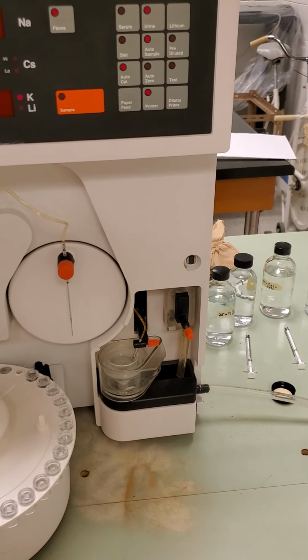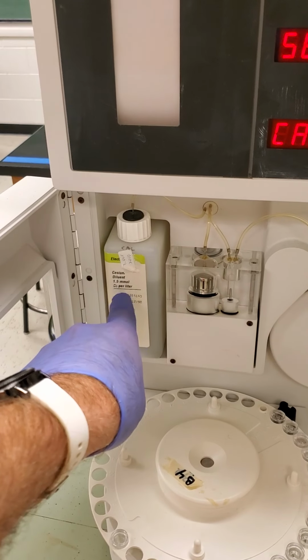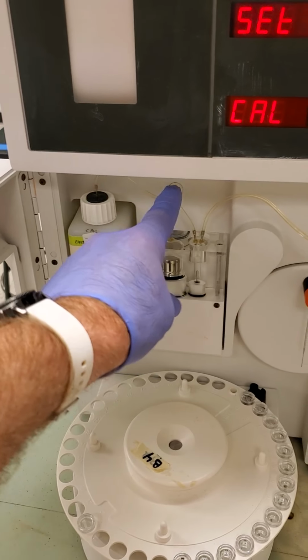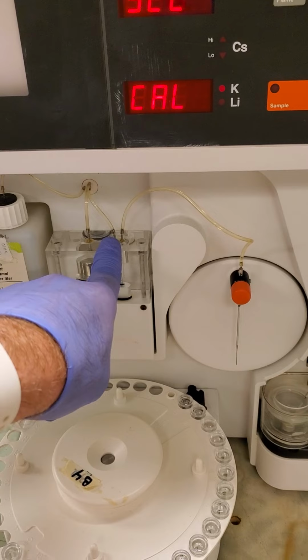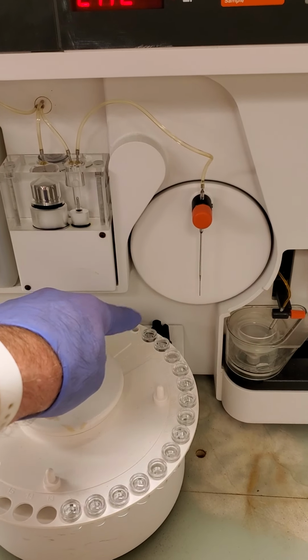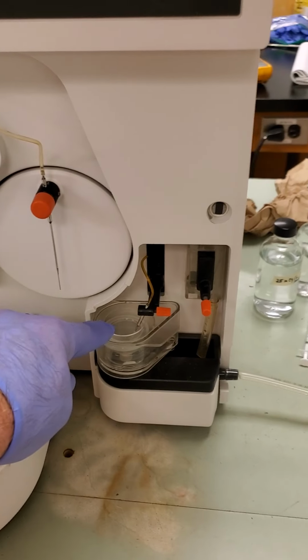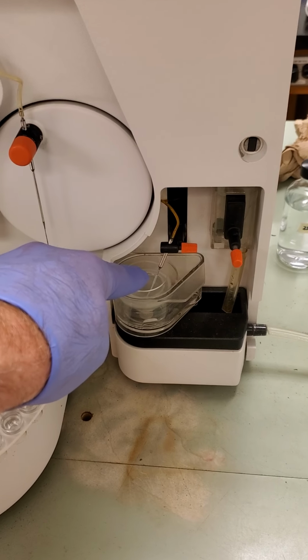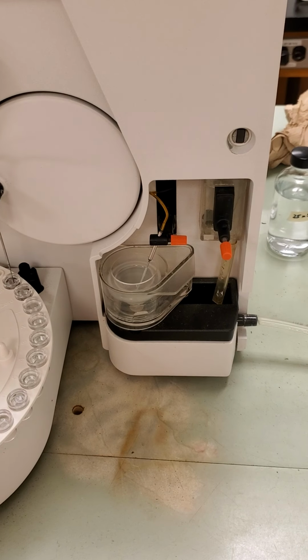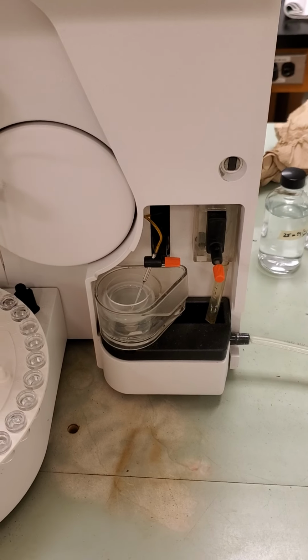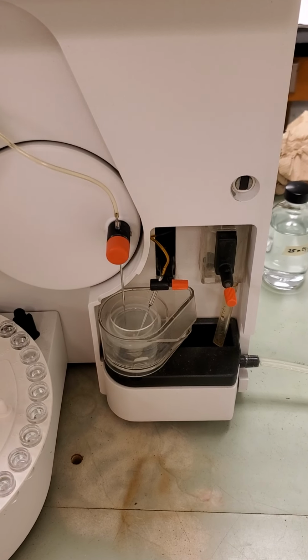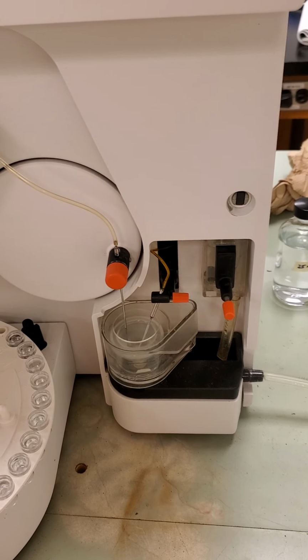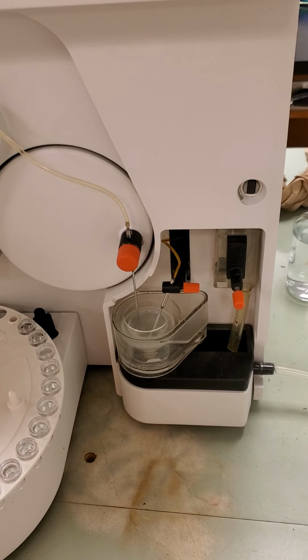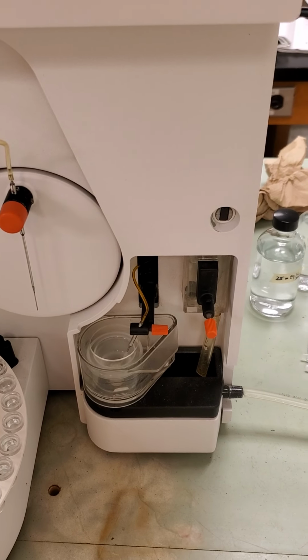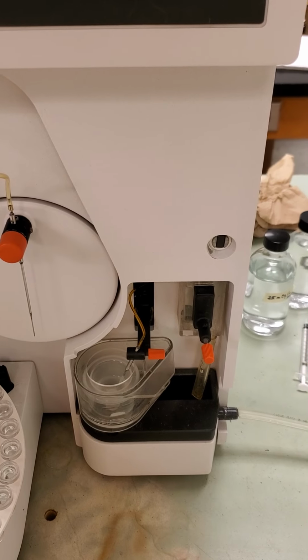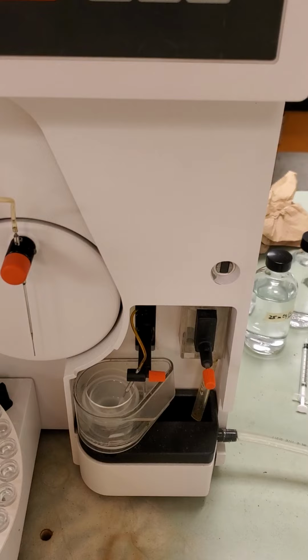So what it does first is it takes, with this large piston here, a sample of the cesium, and then there's an automatic valve back here that switches over, and it mixes it down here with a sample that it pulls up into the sample syringe here, and then both of them are poured into the mixing chamber. It's mixed, and then the sample arm will go in there, pull up the sample. The sample is pulled up using an aspiration system inside the burning chamber. What happens inside that chamber is the compressed air is blown across the feed pipe that is the other end of this pipe, and it creates vacuum. Pulls the sample into the chamber. It's mixed with propane and then ignited and burned at the top of the chamber.